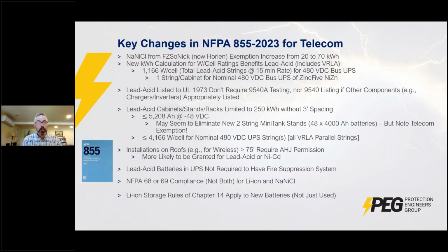Anything above 75 feet requires AHJ permission. That's about the highest they can go up, on a cherry picker or a ladder access. So if it's a rooftop installation above that height, you need to have AHJ permission, but it is more likely to be granted for lead acid and NiCad than some of the other chemistries, because they're basically less combustible. If you have a lead acid battery in a UPS that's not required to have a fire suppression system, typically telecom applications in general don't require fire suppression systems either.